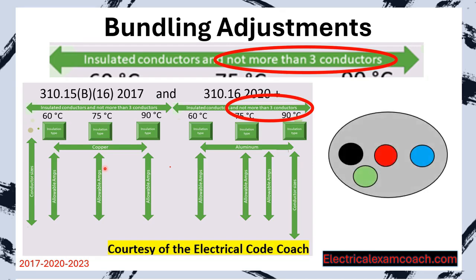Let's imagine that we have a piece of conduit here and we pulled in a black, red, blue, and an equipment grounding conductor. What this table is saying is that those ampacity values listed in this table are true as long as you have not more than three current carrying conductors in a cable, pipe, or raceway. If you do have more than that, then we have to do what's called a bundling adjustment.